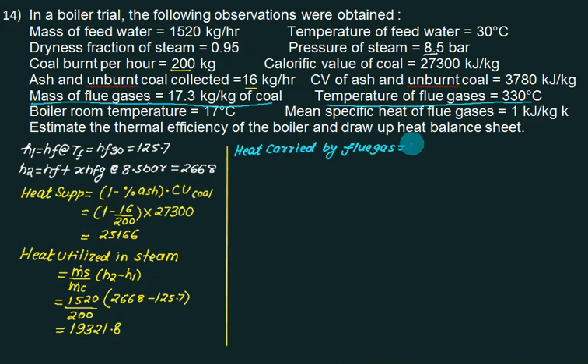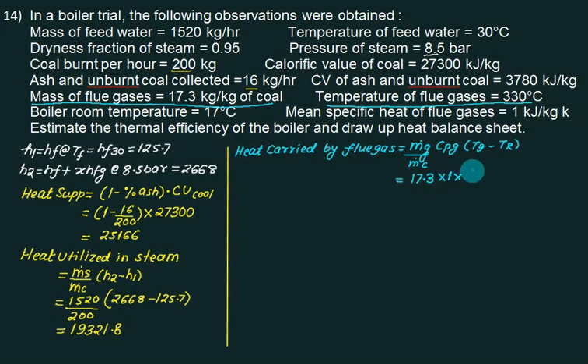So write heat carried by mass of flue gas. It was dry before, so we write G multiplied by Cpg multiplied by (Tg minus TR), divided by mass of coal. What is the mass of gas per kg of coal? 17.3. What is the gas temperature? 330°C. And what is the room temperature? That is 17°C, boiler room temperature is 17°C. This gives the heat carried by flue gas.